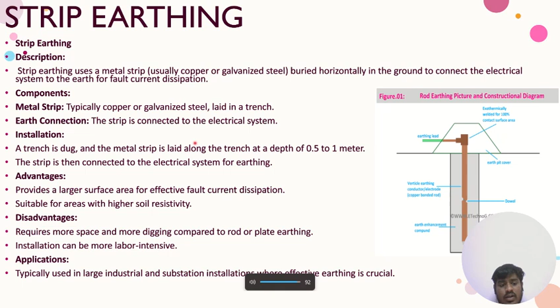Installation: a trench is dug and the metal strip is laid along the trench at a depth of 0.5 to 1 meter. The strip is then connected to the electrical system for earthing. Advantage: provides a larger surface area for effective fault current dissipation, suitable for areas with higher soil resistivity.